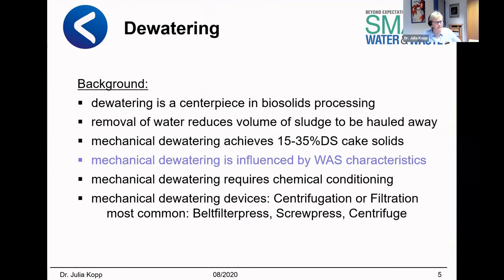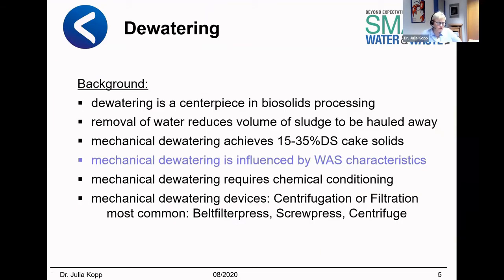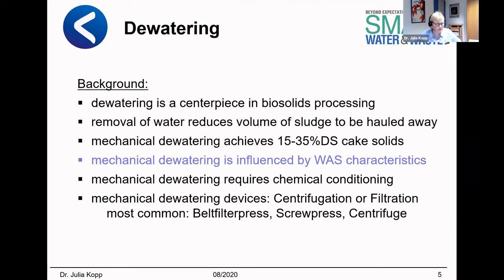Mechanical dewatering is the centerpiece of biosolid processing — that means reducing the volume and mass of sludge that has to be hauled away. If you use a mechanical dewatering device, depending on the sludge characteristics, you can achieve 15 to 35% dried solid in the cake. But the main influence is the waste-activated sludge.